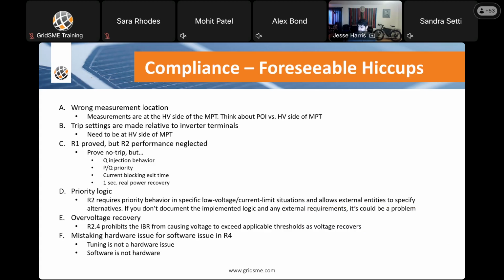So this is just a list of foreseeable issues that could occur that I came up with. By no means is this list exhaustive. So the first, it could be wrong measurement location. Say you have the HV side of an MPT and then you have a 300-foot line just over the fence that connects to your POI, and you're monitoring the POI instead of the high voltage side of the MPT, you're going to be non-compliant. So just keep that in mind. Trip settings are made relative to the inverter terminals. Remember, everything is at the HV side of the MPT in PRC-029. So all that stuff doesn't matter. All those ride-through zones were at the HV side, and they need to be monitored there.